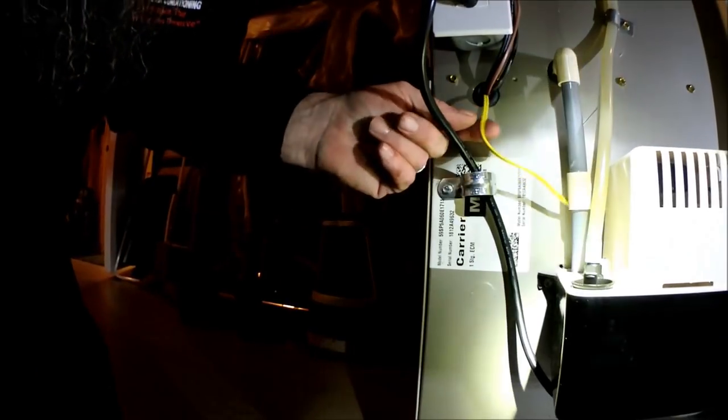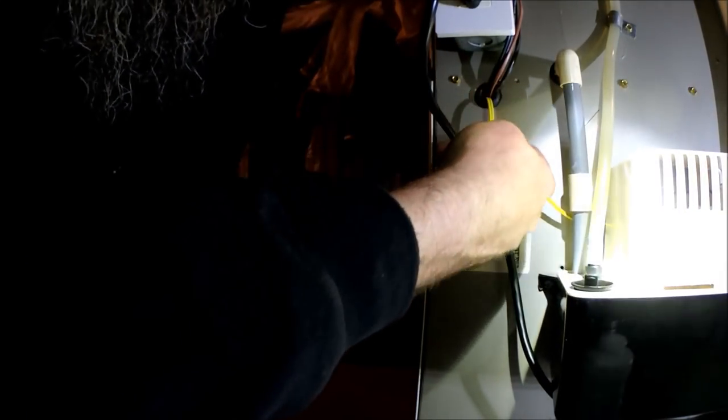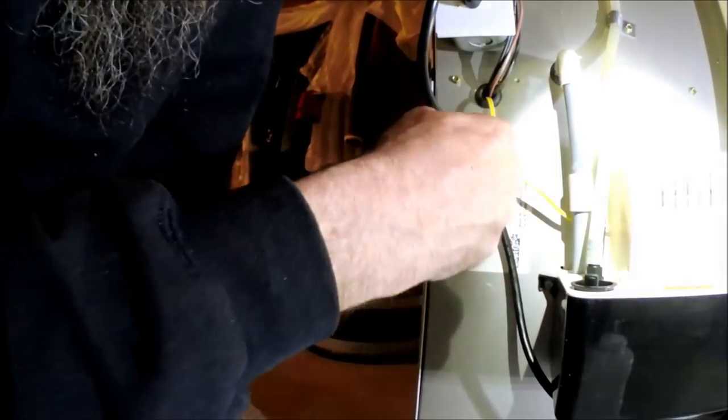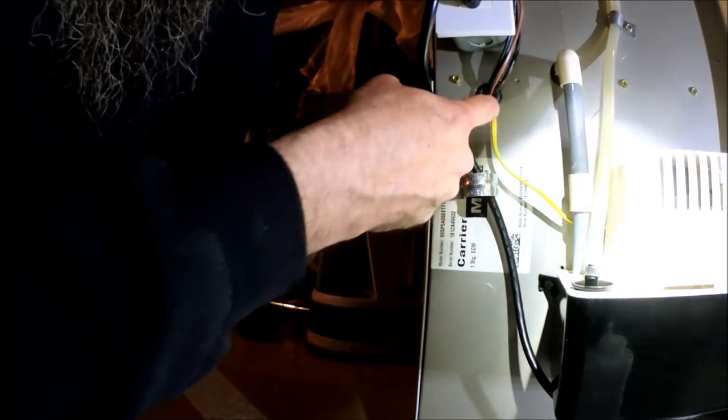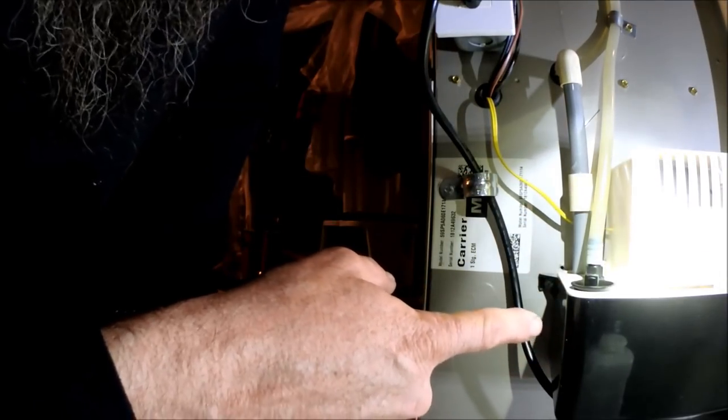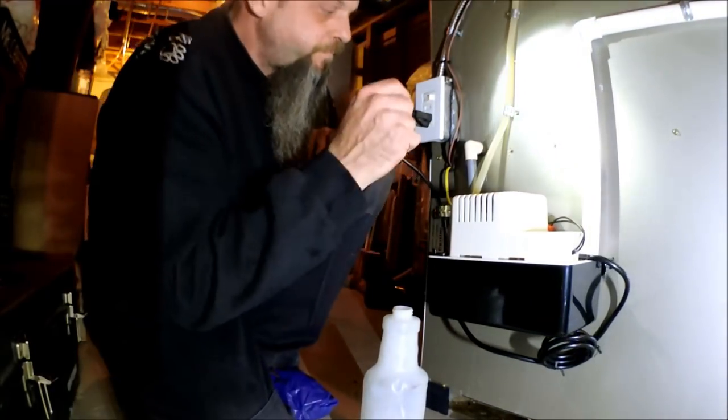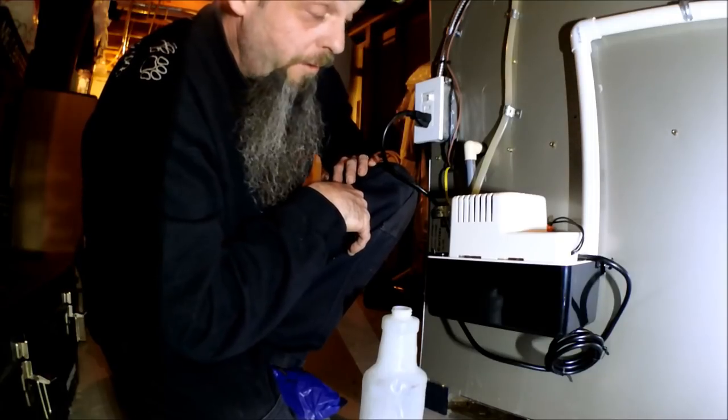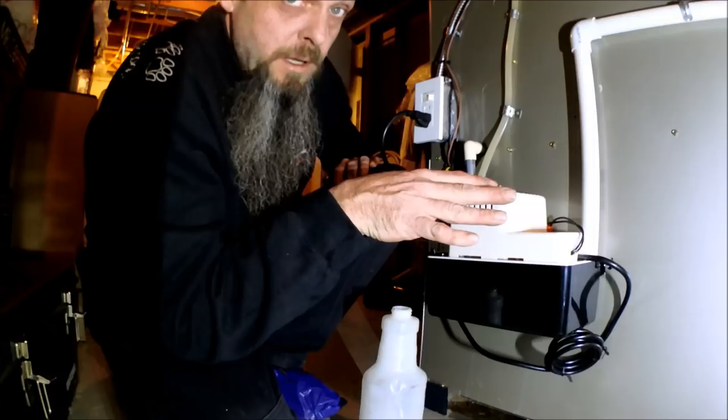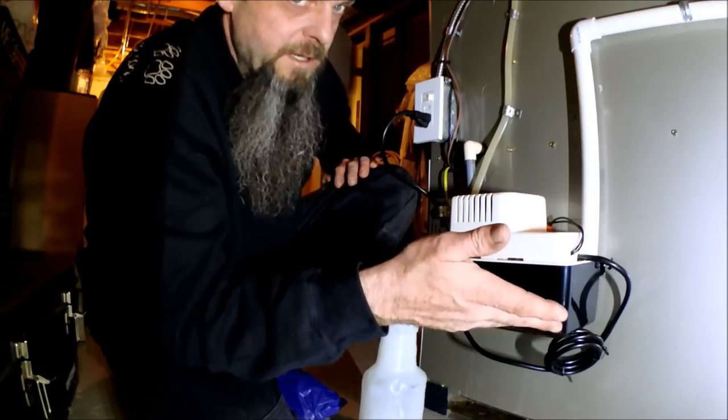But the way the safety switch wires in, actually this goes to the control board. R comes out, 24 volts comes out through the pump and back to the actual thermostat R wire. So then all the power has to go through here. So if this condensate pump fails, either air conditioning or heating stops the whole system because we're producing water. Heating and air conditioning, also the humidifier too. So we want to completely shut the system down if we run into condensate overflow, because we don't know what it's from. But at least I'm stopping any damage from happening.